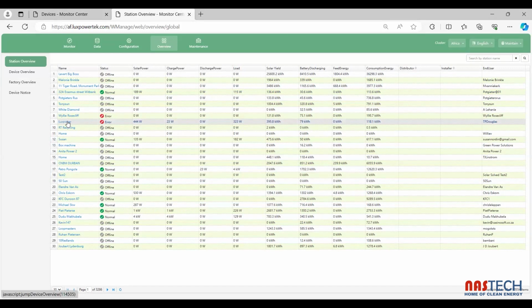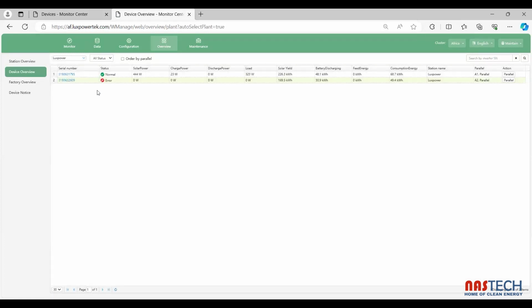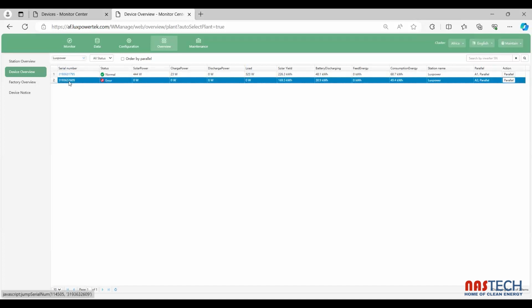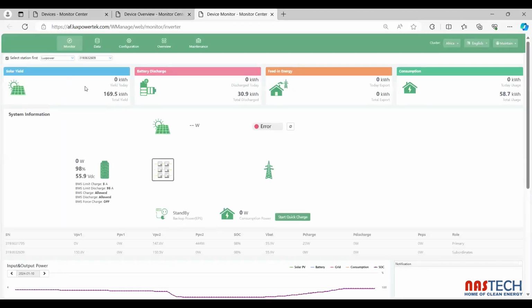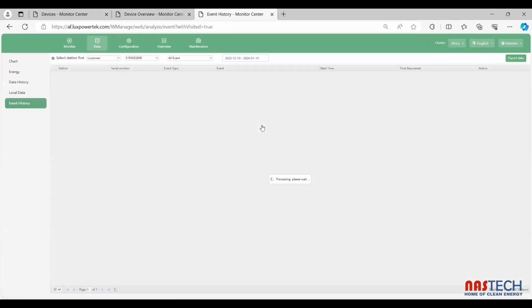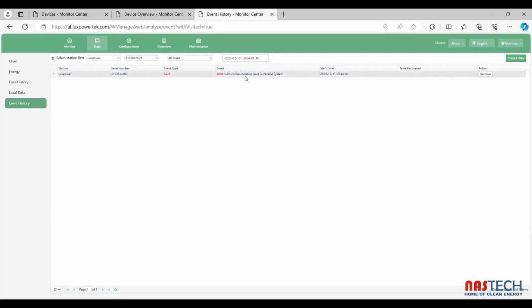For example, let me just go to this one. It has an error. I see these two are in parallel. There's two inverters and this one has an error. So as an example, take a look at what that error is. So this becomes a button now, and I can see what that error is. So it says at the event history. So for this inverter, it will now bring me up all the events. There's a fault, CAN communication fault in the parallel system. So I'm not going to fiddle with this client's. I just wanted to show you.